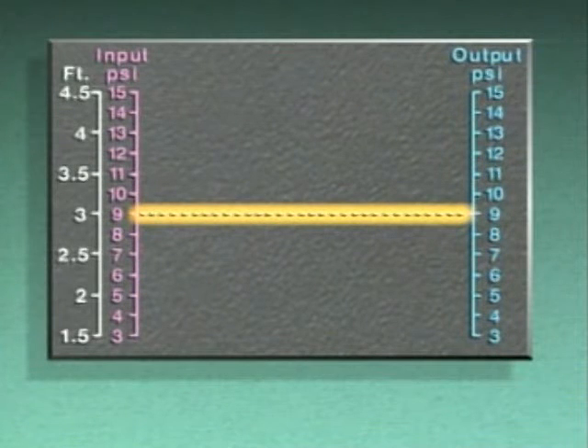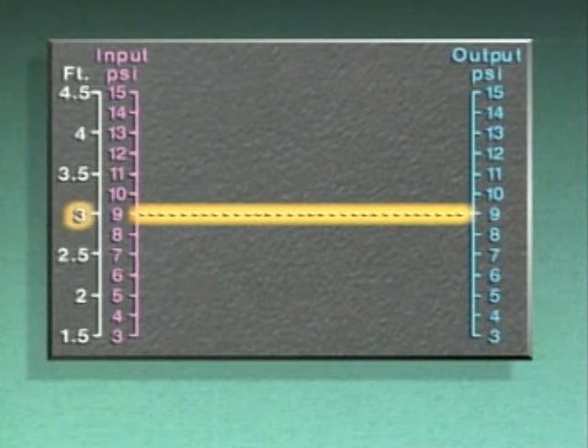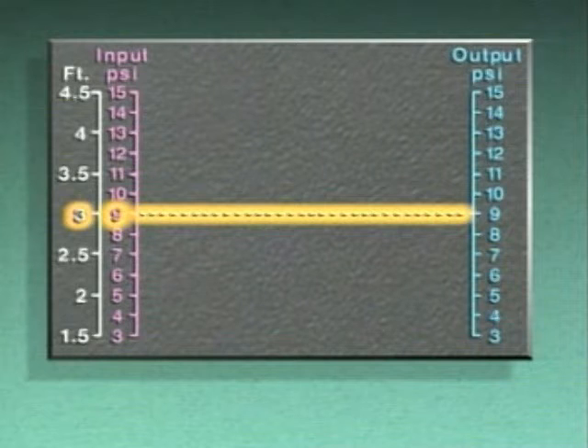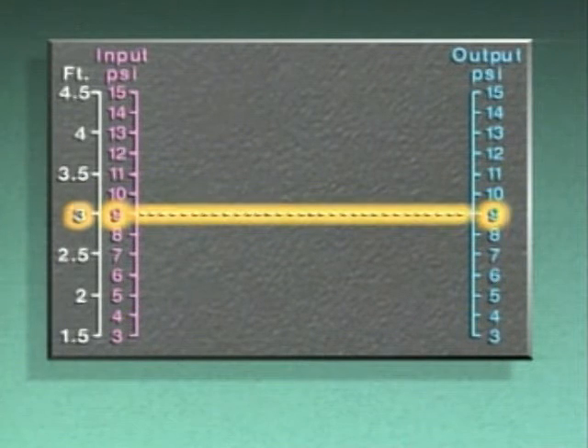The dashed horizontal line represents the set point for the water level. In this example, the set point is 3 feet, which is equivalent to a 9 PSI input signal to the controller, and a 9 PSI output signal from the controller.